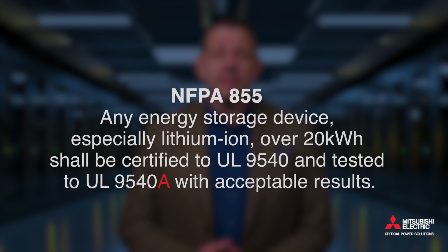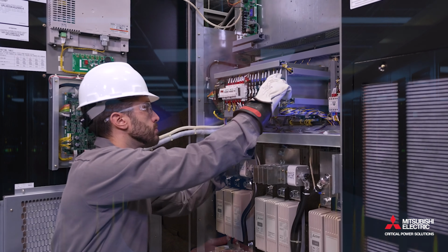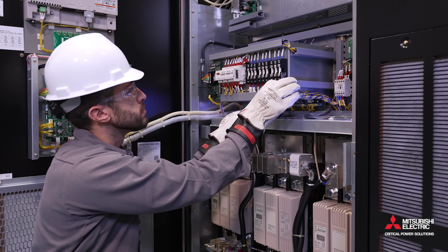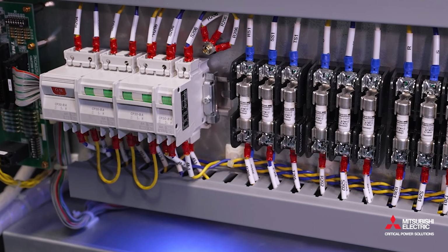NFPA 855 is a standard for installation of stationary energy storage systems. In general, NFPA 855 states any energy storage device, especially lithium-ion, over 20 kilowatt hours, shall be certified to UL 9540 and tested to UL 9540A with acceptable results. In recent years, UL and NFPA 855 have considered a UPS system to be an energy storage system and therefore now subject to UL 9540 requirements.